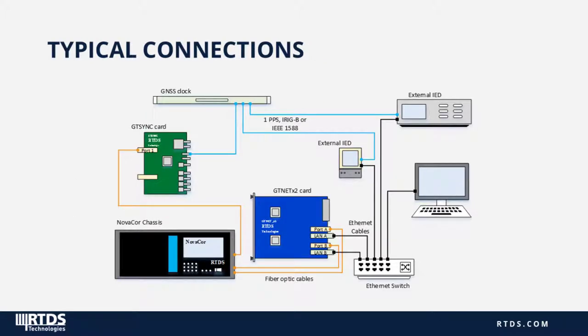A typical setup would include an external GNSS clock providing a time reference to the RTDS GT Sync card, which is connected to the central processor via fiber cable on a dedicated port on the NovaCore. That time reference is also provided to two external IEDs. The RTDS simulator's GTNet card receives simulated data via fiber cable and puts them onto the local area network via Ethernet, and the user's PC is also connected to the switch.